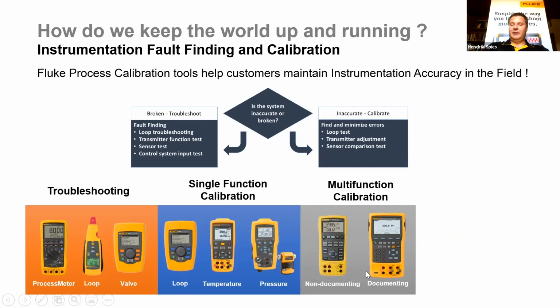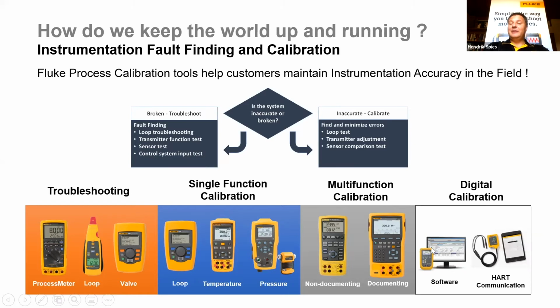And then we go to the documenting calibrators, which typically will document the as found, the changes as done, and as left, and it can do it via HART protocol as well. Last but not least, we have the digital calibration. We connect to software, and we have our documenting multifunction calibrators that you use in the field that will then receive calibration data from the software: what needs to be calibrated, at what parameters. And when you are finished, you download the as found and as left calibration done in the field back into the software. So then you can do some nice calibration reports.